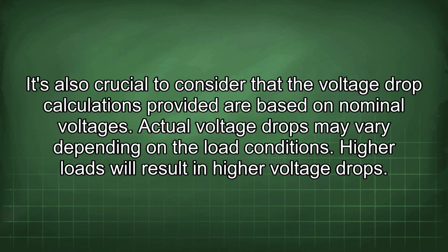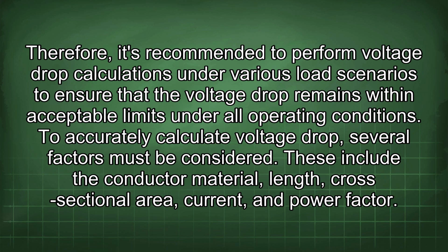It's also crucial to consider that the voltage drop calculations provided are based on nominal voltages. Actual voltage drops may vary depending on the load conditions. Higher loads will result in higher voltage drops. Therefore, it's recommended to perform voltage drop calculations under various load scenarios to ensure that the voltage drop remains within acceptable limits under all operating conditions.